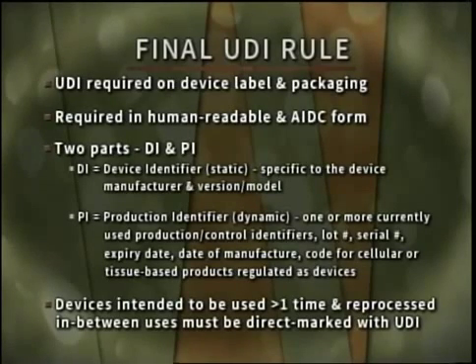There are two components of the UDI. There's a device identifier, or DI, that really reflects the manufacturer and model. And then there's the production identifier, or PI, that really provides additional identifying information. So it could be the lot number, serial number, expiration date, date of manufacture. And then there's a specific code for cellular or tissue-based products that are regulated as devices. So really providing that extra information.